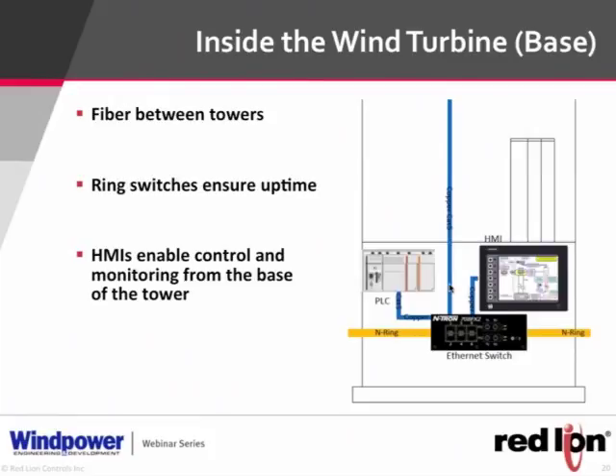The ring ensures uptime: if a fiber optic cable is cut anywhere, the ring heals in 30 milliseconds. PLC peer-to-peer communications between towers would never even detect the outage. The HMI allows you to monitor the network from the base of the tower without climbing. This is our G3 HMI, paired with Crimson software for easy programming, and the 708-FX2 Ethernet switch — our sweet spot switch for this type of application.